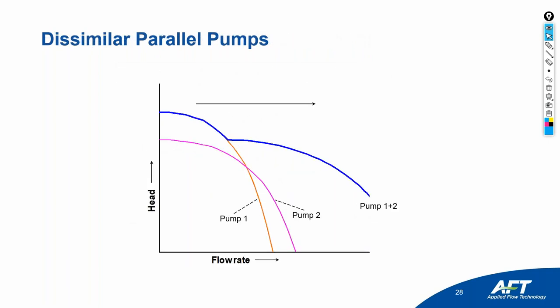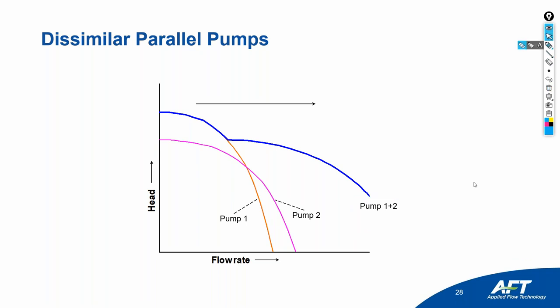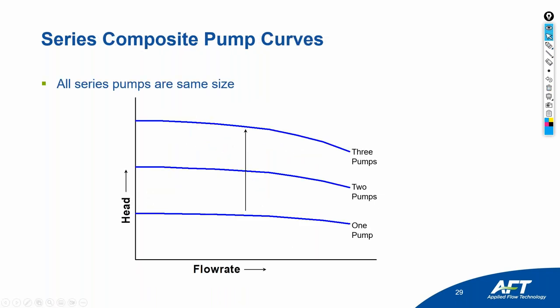If you have dissimilar pumps with different pump curves operating in parallel, Fathom accounts for how they add together, producing an odd-shaped composite system curve. When pumps are in series and the same size, head simply adds.